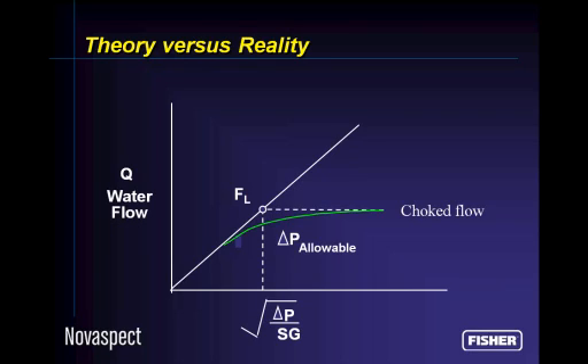Boiling of the water to steam occurs within the valve, and you can see that there is a constant that we call F sub L. That is the valve geometry coefficient, or the valve recovery coefficient. Some people call it different names. That is the coefficient that determines, for any given valve in any given application, where along the delta P x-axis this departure from theory to reality takes place. And this is important to know because it helps guide us in our selection of a control valve to address this problem.